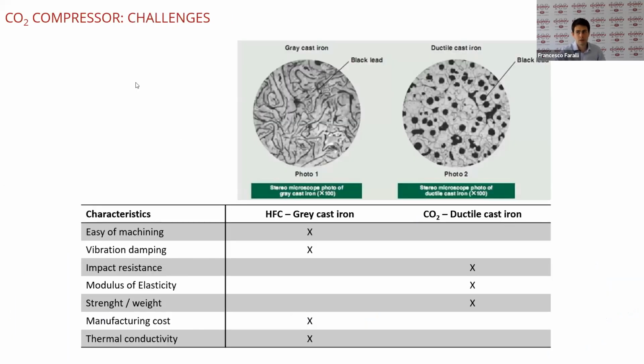If we speak about the crankcase of the compressor, instead of using gray cast iron like for HFC compressors, we are using ductile cast iron. That for sure is much more expensive. It's roughly 50% more expensive than the standard cast iron that we use for Freon. And it's also not as easy to machine as the gray cast iron. But on the other hand, it's quite strong and can withstand the higher pressure of transcritical CO2.